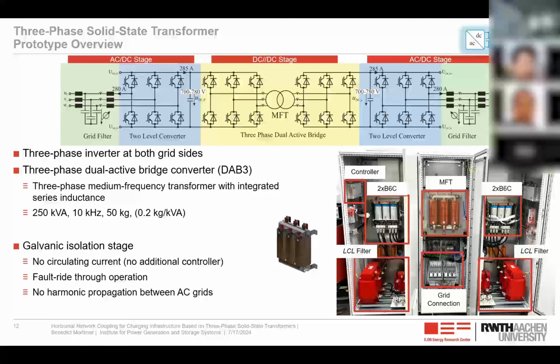So it's quite handy. And we chose this approach with a galvanic isolation stage because with this structure, we do not have any path for circulating currents that might occur, especially during fault ride-through operation. We do not rely on controlling some common mode voltages, so we can really eliminate the circulating currents and thus have full fault ride-through operation. And further, since the control bandwidth of the DAB is quite high, we can also avoid any harmonic propagation between the two AC grids, which might not be the case if we use just a simple back-to-back converter.